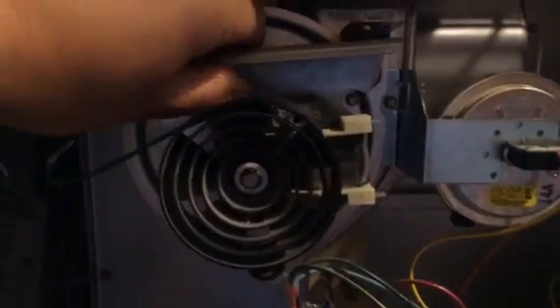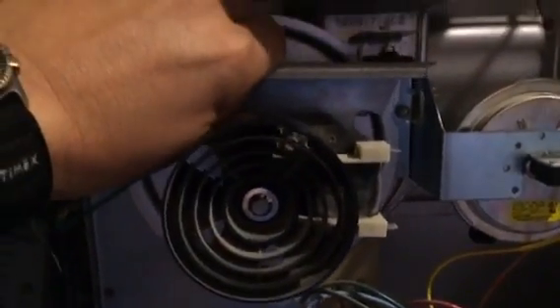I've removed all 3 mounting screws. I'm going to pull the motor out. So it turns out that I have to remove the 3 screws behind, because the blower part of the motor is actually inside that housing, and therefore that whole housing cover has to come off. That housing cover being this part right here. So I'm just going to remove that. So after taking out the housing cover and bolts, I am now going to remove the whole unit.